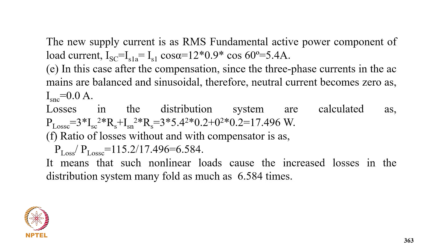So the ratio of losses without and with compensation is 115.2 divided by 17.496, so it becomes 6.584. It means that such a nonlinear load causes increased losses in the distribution system, as much as 6.584 times.